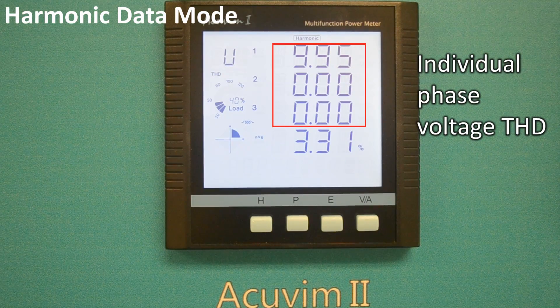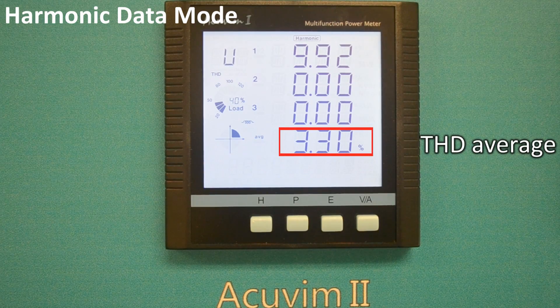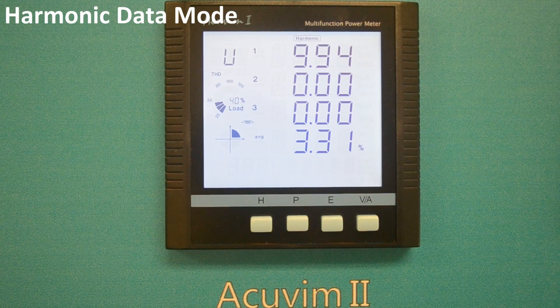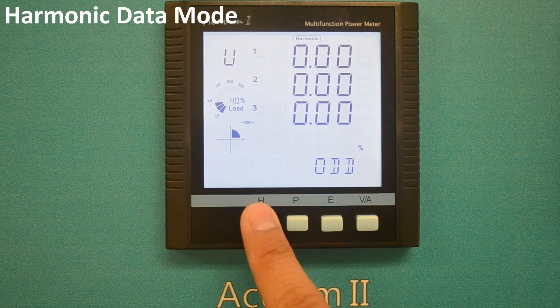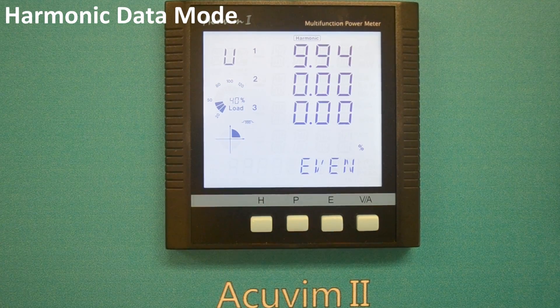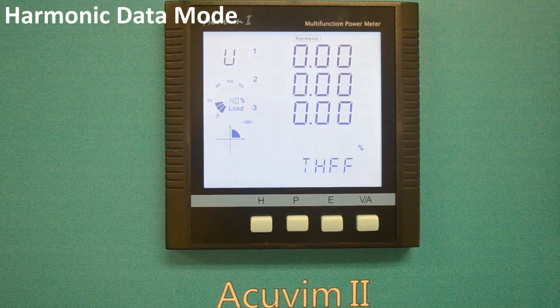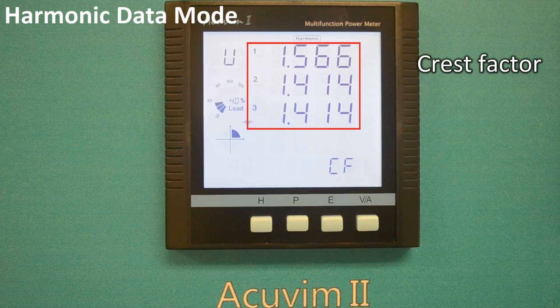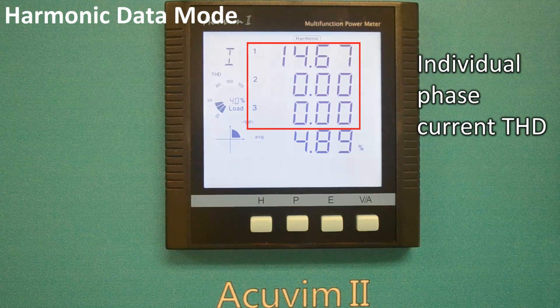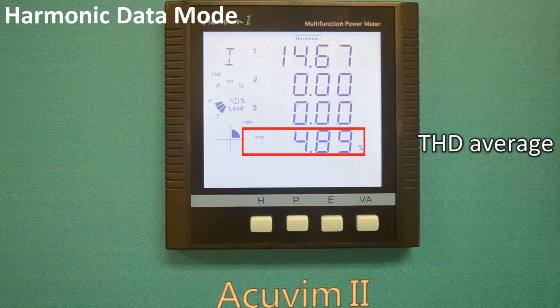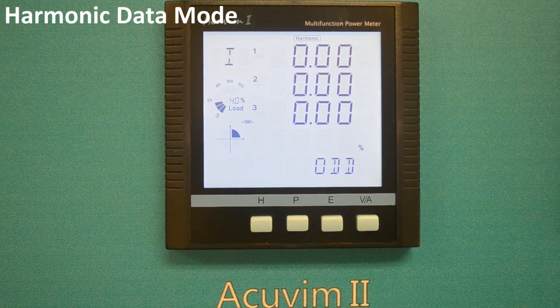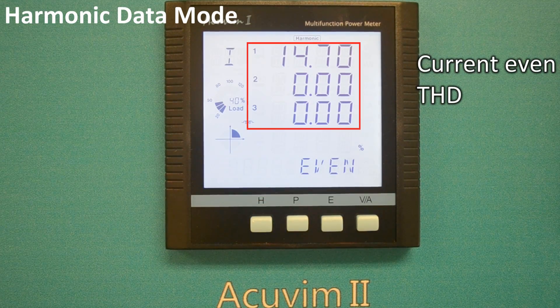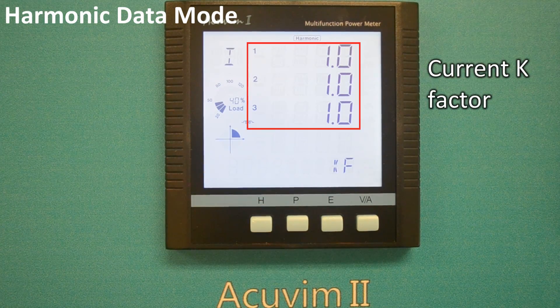The first screen in the harmonic data mode is individual phase voltage THD and THD average. Pressing the H key will change the screen to voltage odd THD, voltage even THD, voltage THFF, voltage crest factor, individual phase current THD and THD average, current odd THD, current even THD, and current K factor.